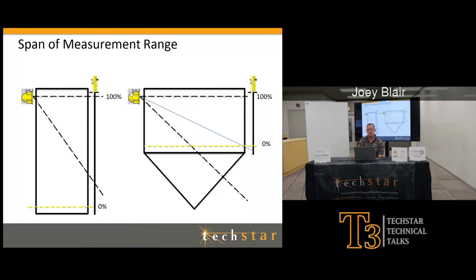So let's talk about installation and a bit about our measurement spans. We used to have two different pictures here, two different vessels. Most of our collimation angles, our beam angles, will be 45 degrees. When you look at the back of your source holder and check the model number - at least on a Vega - it'll say dash 45, telling me I have a 45-degree beam angle, or it'll say dash 0.